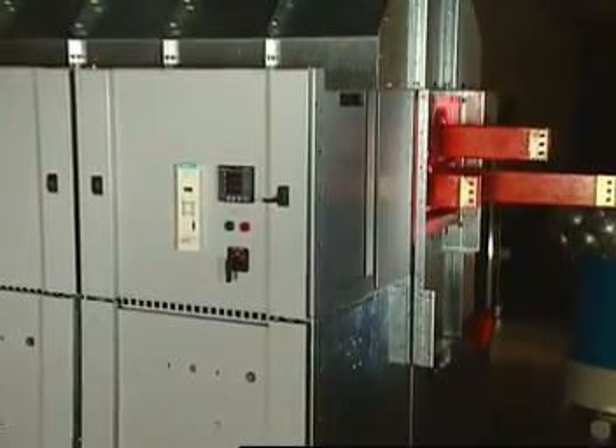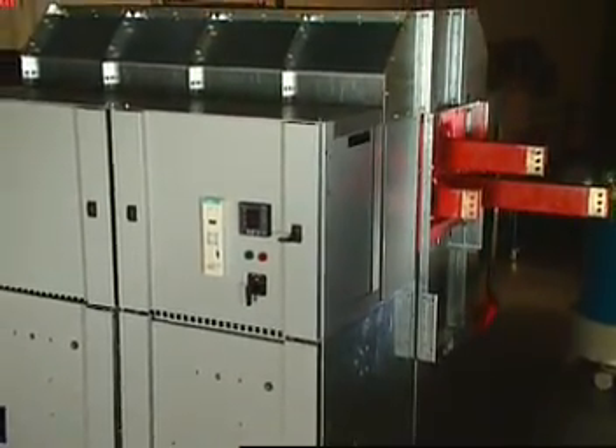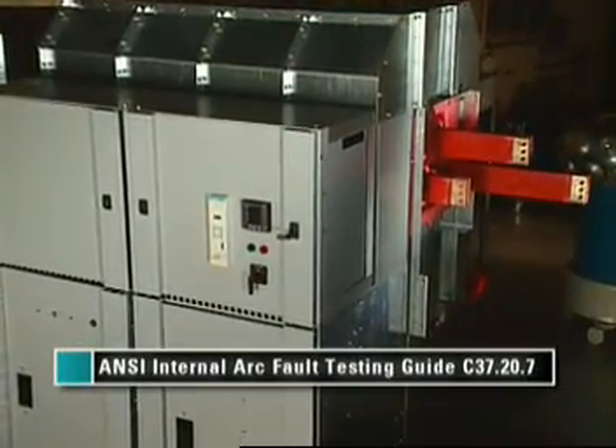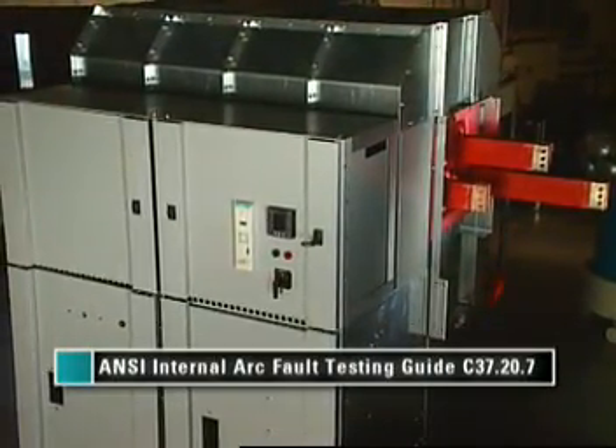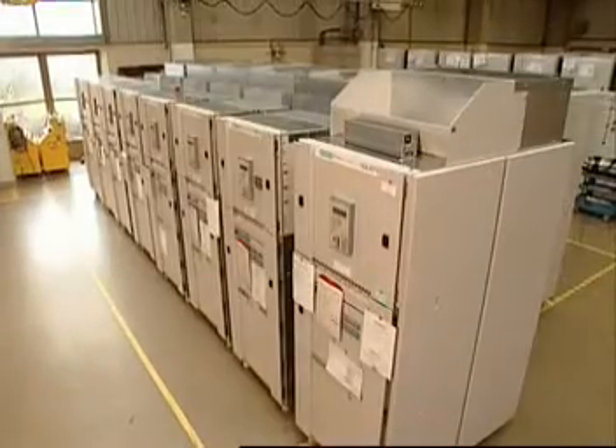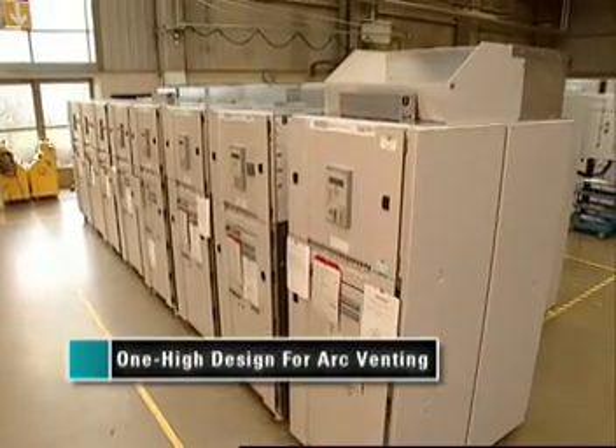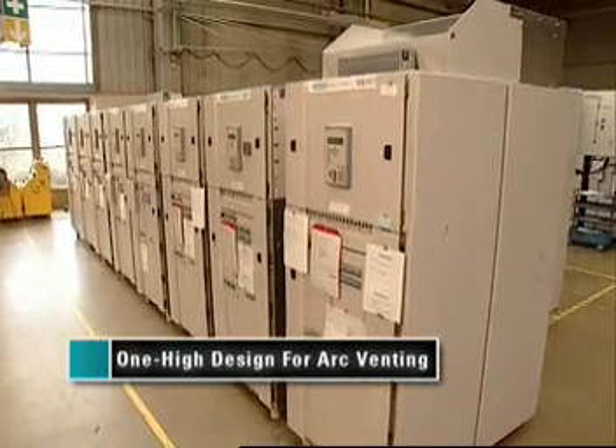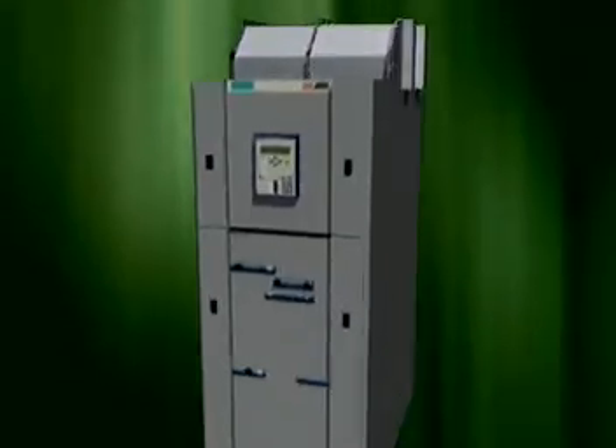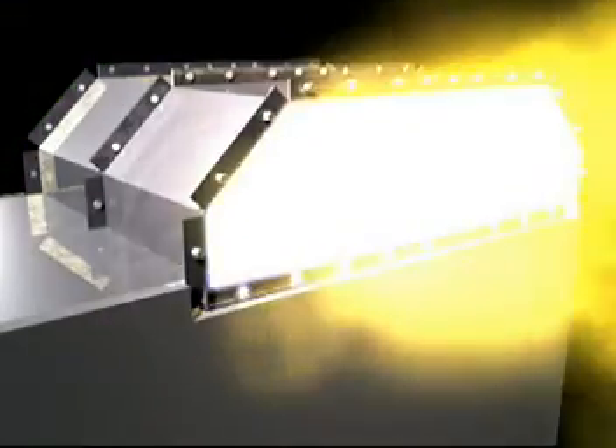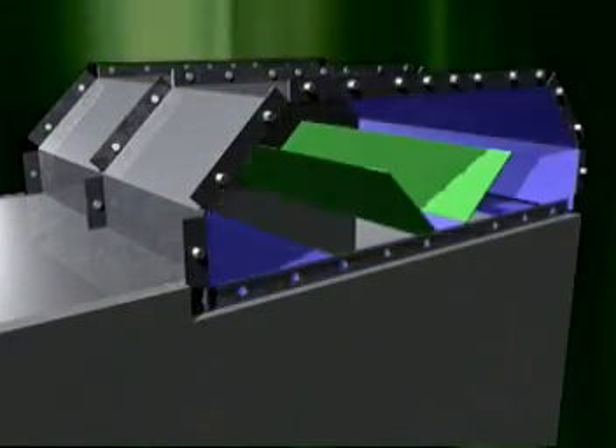The NXAirP will be available with or without the arc venting features. However, with the increased importance of operator safety reflected in the newly issued IEEE standard, arc venting will become commonly specified in North America. To offer the safety of arc venting, we developed the NXAirP with a one-high breaker design. Many switchgear operators aren't used to this one-high design, so we've had to address a lot of questions about the NXAirP. As it turns out, only 15 to 20% of switchgear units in the United States have the breaker in the top compartment. We feel the arc venting benefits of the one-high design far outweigh any loss of stacking ability.